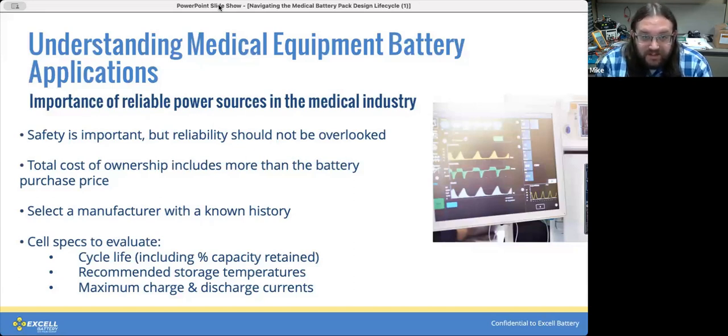Few important things to consider when evaluating the reliability of the battery. Generally start with the manufacturer and type of the cells. They make up the majority of the assembly, and trying to stick with high quality cells from known manufacturers that have the history to support it and will likely continue to be around for a long time can save a bunch of headache.